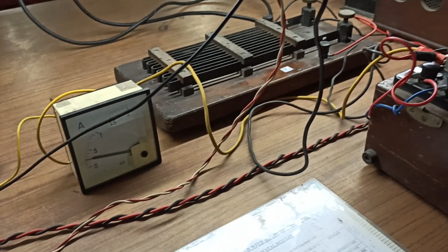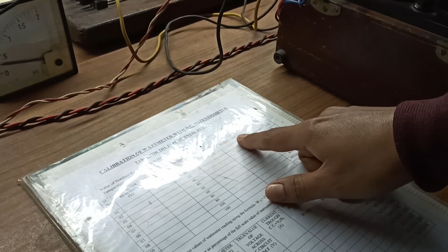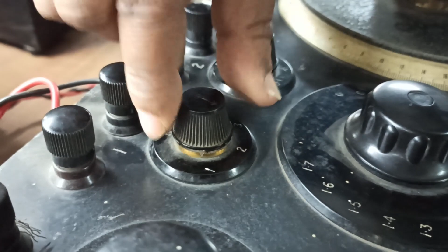Now we have checked the output voltage V1 for 20 watt, with link and without link condition. We need to take the value of the meter also for these two readings. Now we will calibrate the current coil. That means we will check the voltage drop V2 across the resistance R1, which is connected in terminal 3. So we will change the selector switch to 3 and the range as well to 0.1.